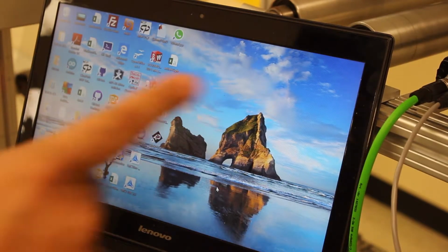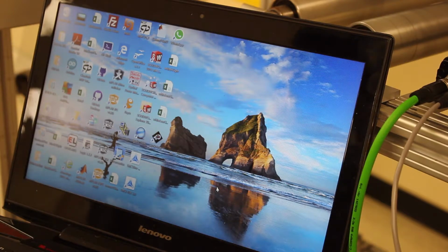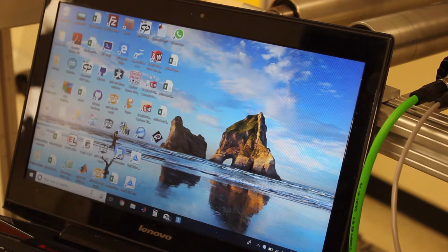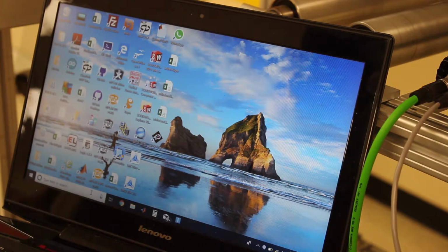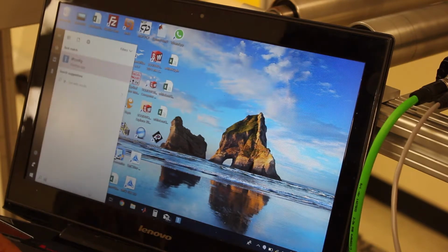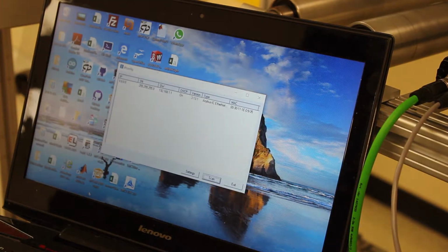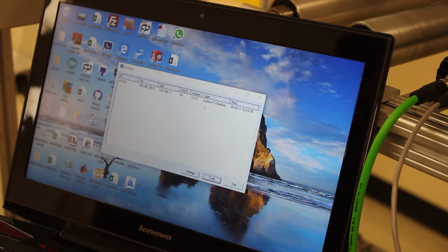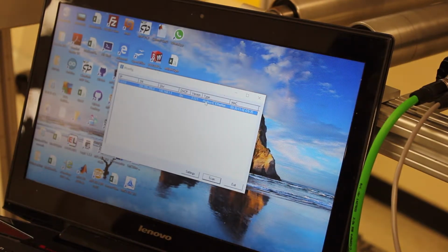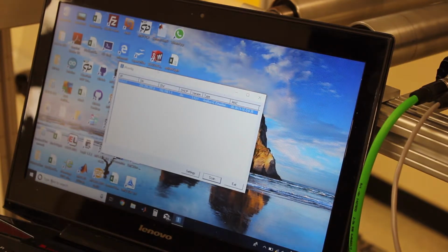The next thing that we want to do is to connect the sensor to the PLC. One of the first things that we want to do is find the IP address. Once the sensor is connected and powered up and connected to your network device, you can pull up a utility called IP config. We have information about that on our website. Once you open up that program, it will show what device there is and what the IP address of that is. Right now, the device is set to DHCP automatically, and it has an IP address 0.0.0.0. This is happening mainly because the gateway doesn't match. So what we would do is make sure that the gateway matches.